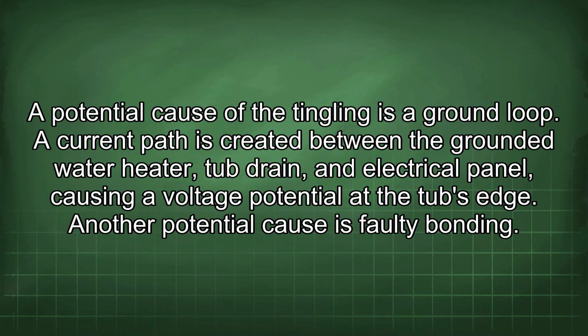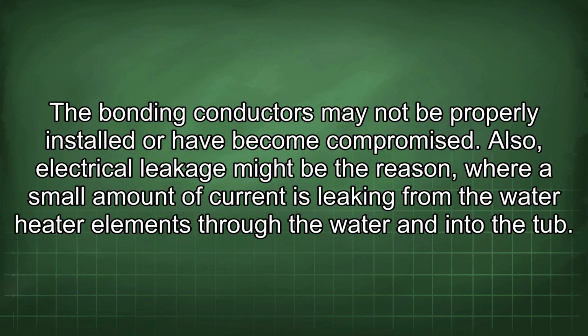A potential cause of the tingling is a ground loop. A current path is created between the grounded water heater, tub drain, and electrical panel, causing a voltage potential at the tub's edge. Another potential cause is faulty bonding. Bonding conductors may not be properly installed or have become compromised.